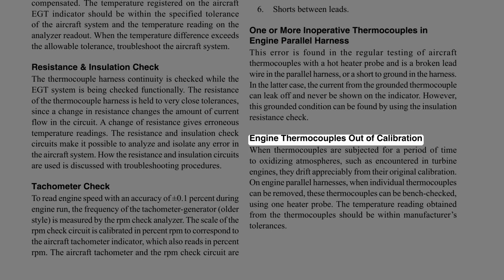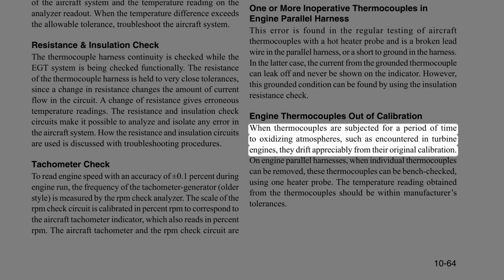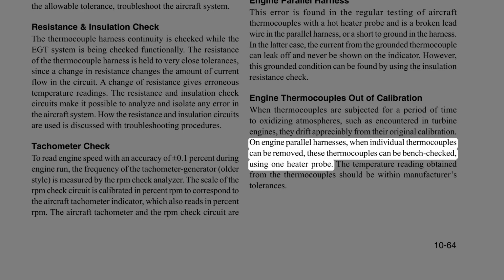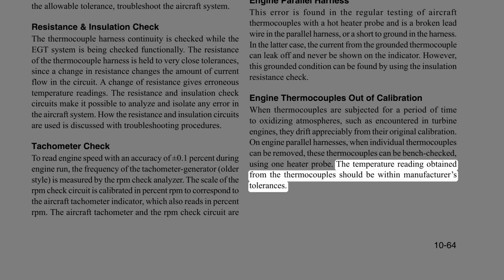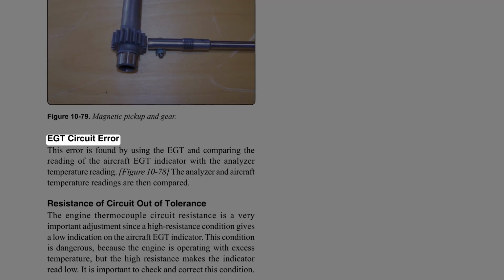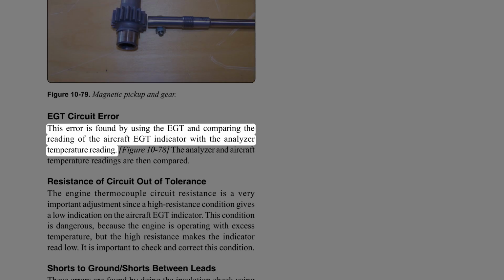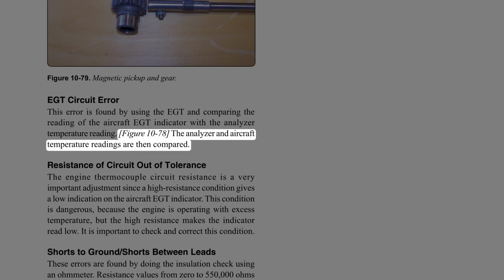Engine thermocouples out of calibration. When thermocouples are subjected for a period of time to oxidizing atmospheres, such as encountered in turbine engines, they drift appreciably from their original calibration. On engine parallel harnesses, when individual thermocouples can be removed, these thermocouples can be bench-checked using one heater probe. The temperature reading obtained from the thermocouples should be within manufacturer's tolerances. EGT circuit error. This error is found by using the EGT and comparing the reading of the aircraft EGT indicator with the analyzer temperature reading. Figure 10-78. The analyzer and aircraft temperature readings are then compared.